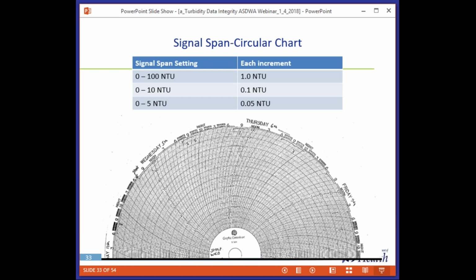Here's an example of where signal span can be an issue. We still have some small water utilities that use chart recorders. This is a 10-inch chart recorder paper from a small town. And you can see here, if you have the signal span setting at 0 to 100, then each of those tiny lines there is 1 NTU.